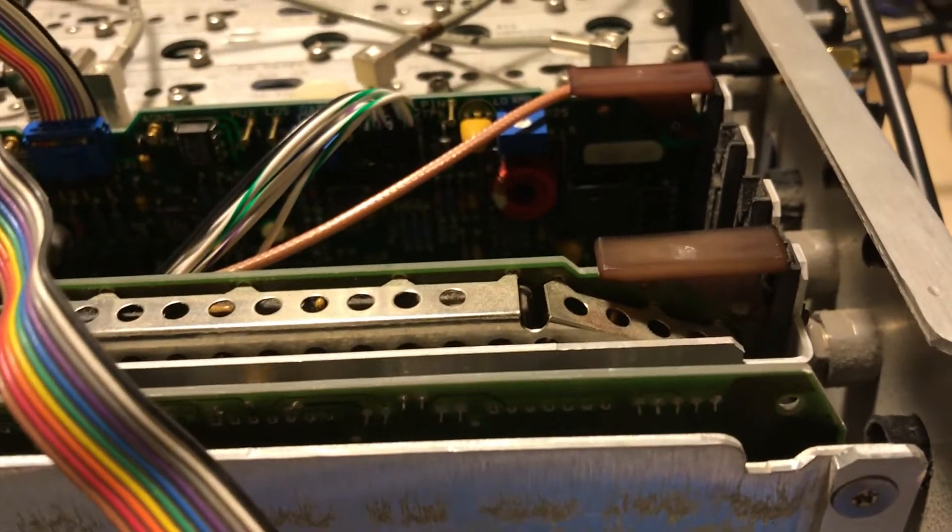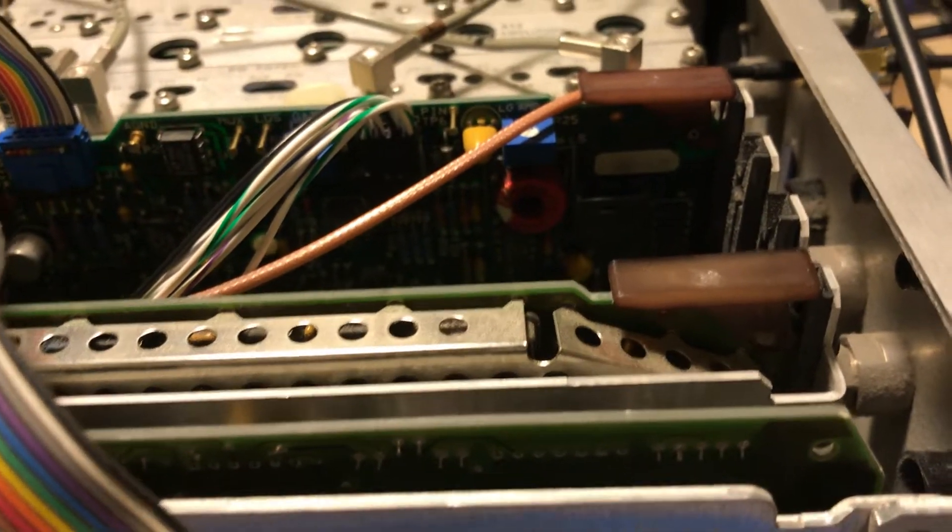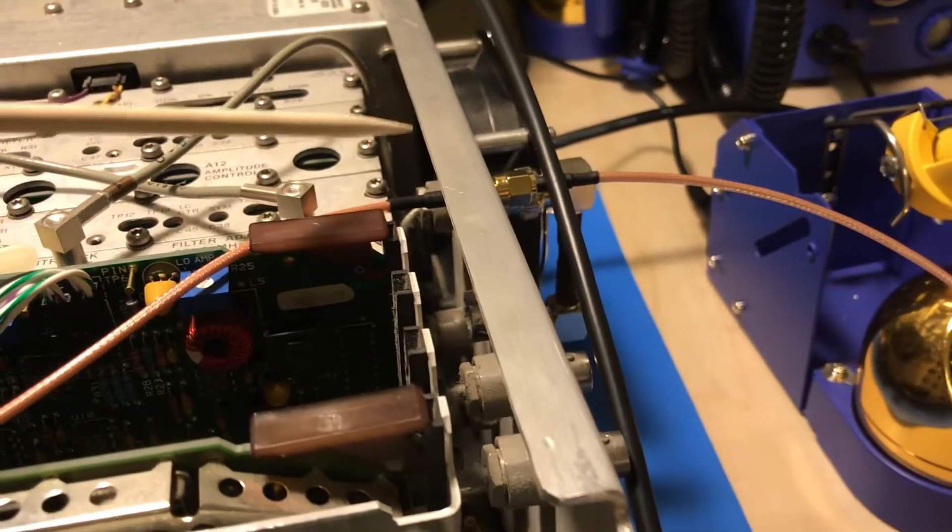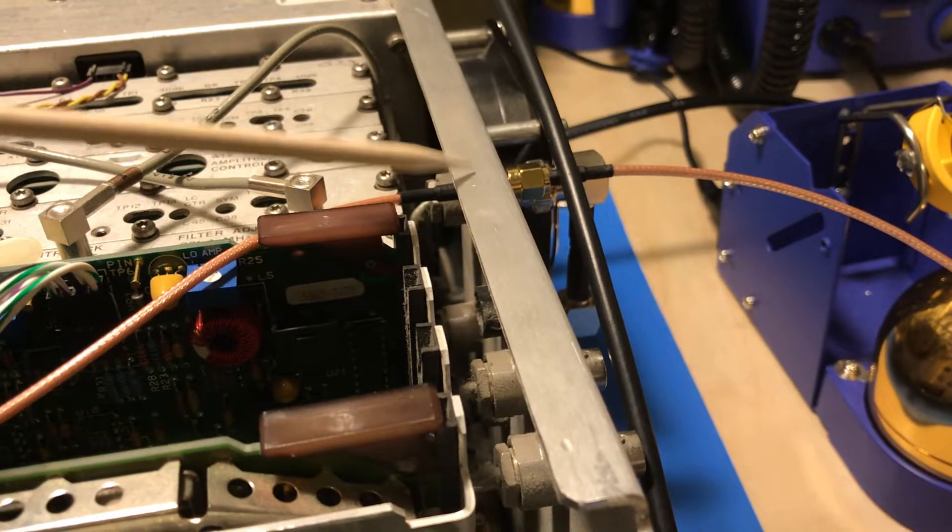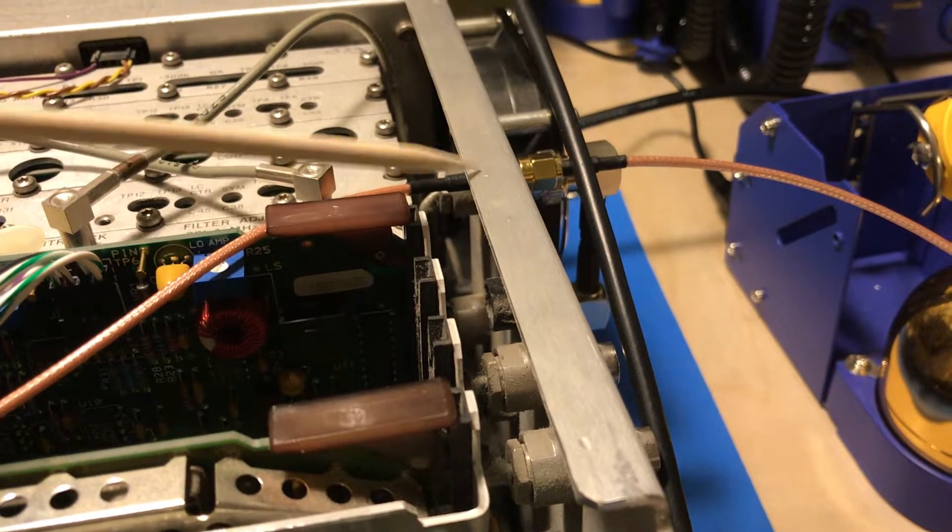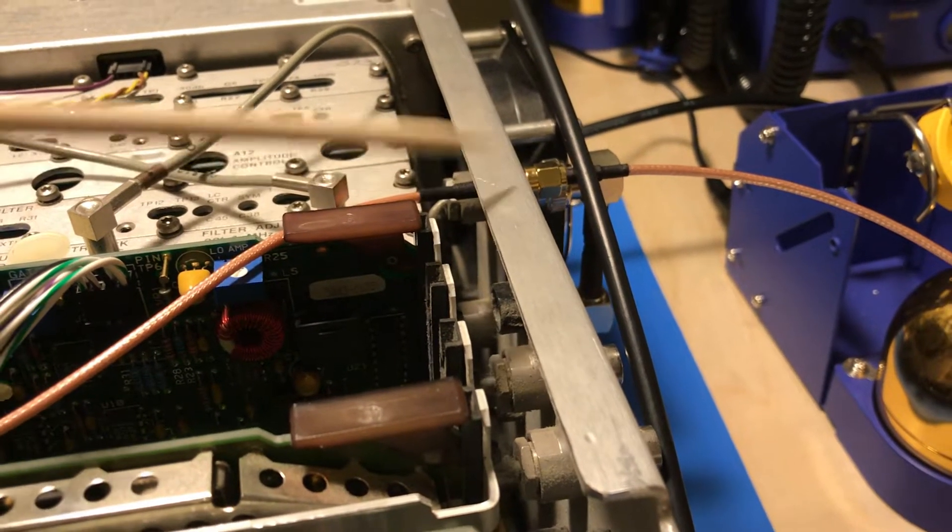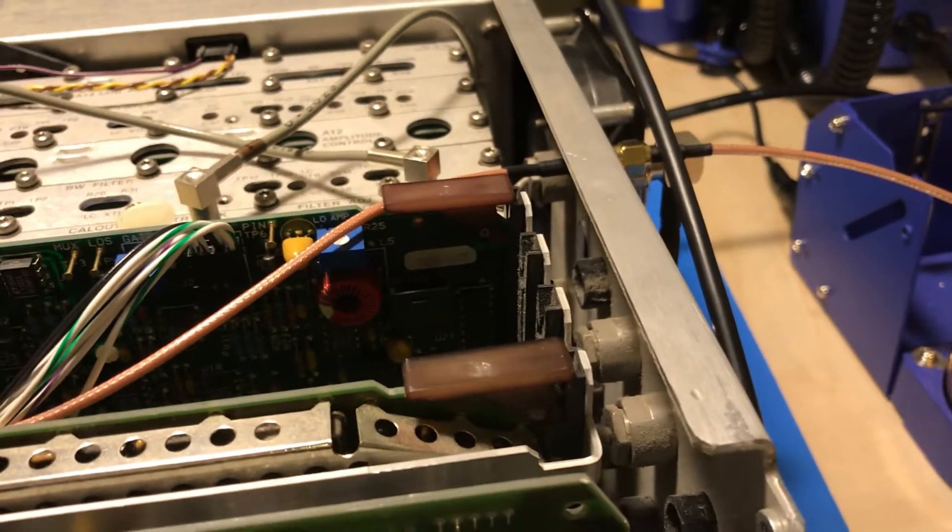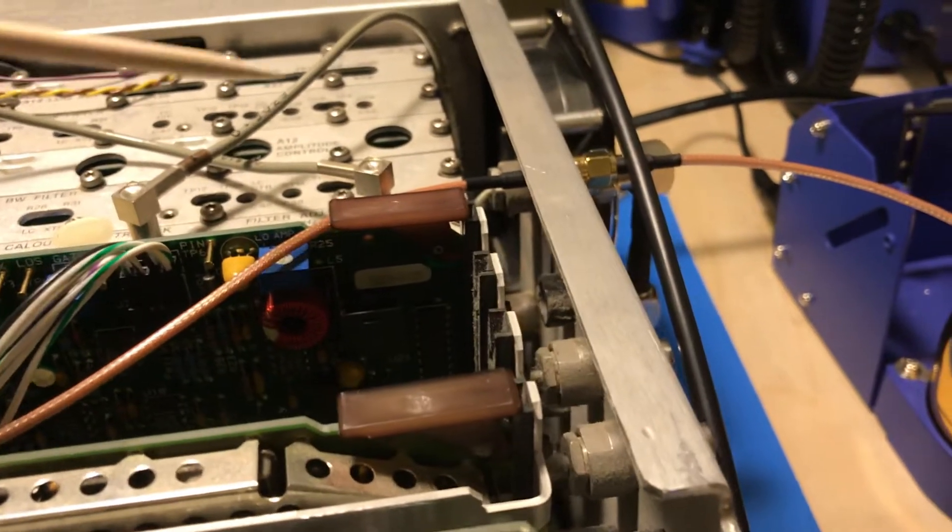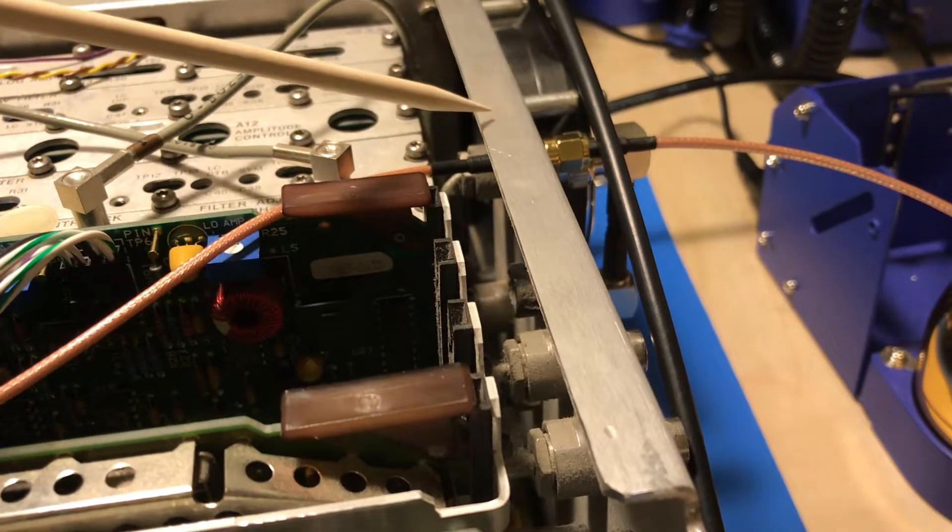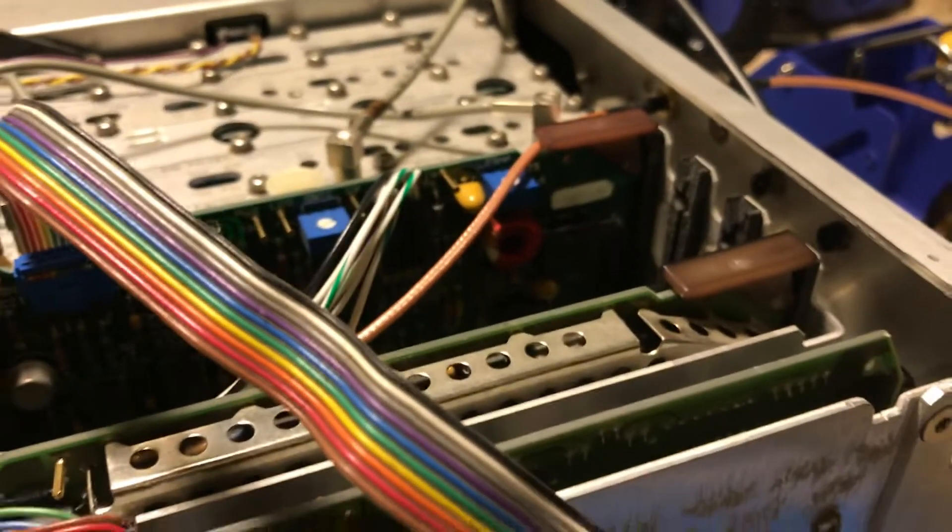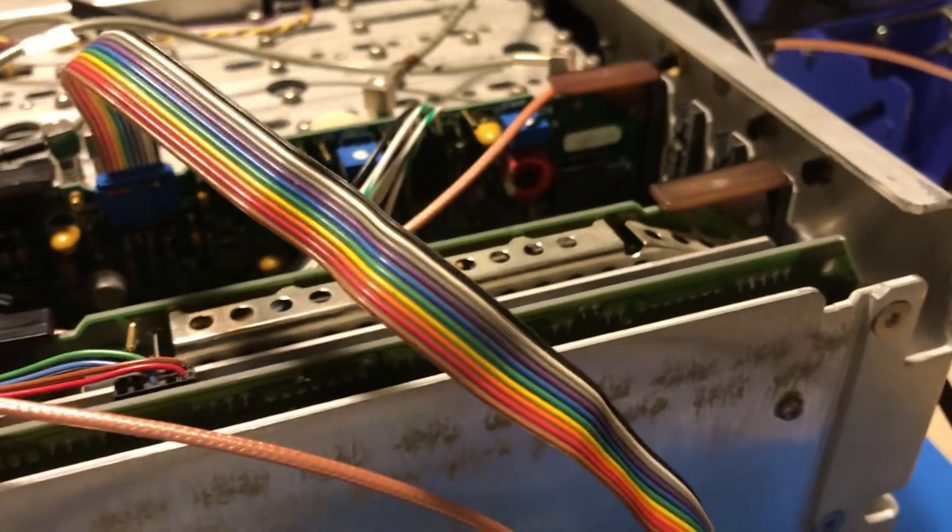Set that up. One thing I did learn is that with this LO out on the back here, if that's not terminated at 50 ohms, you'll get an error message on the unit saying LO unlevel. Make sure if you're not going to use the output, keep that terminated at 50 ohms. I learned that.